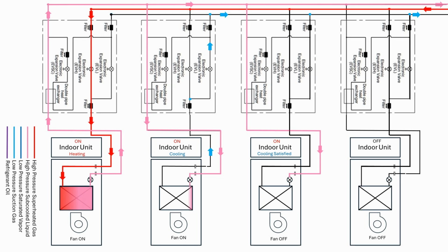The liquid refrigerant entering the indoor coil passes through an expansion valve which will meter the refrigerant, causing a pressure drop, changing the state to a saturated vapor. As the low-pressure saturated vapor travels through the indoor coil, it is being superheated into a suction gas, removing heat from the space. The superheated suction gas is sent back to the branch selector box and routed through the low-pressure expansion valve to the suction line to be taken back to the outdoor unit.